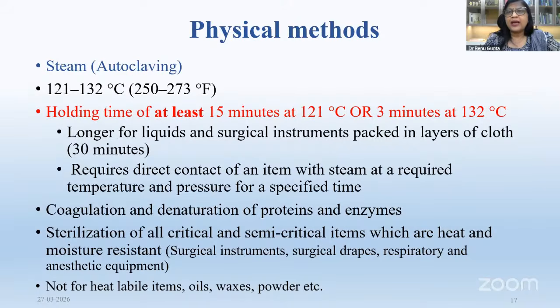This is for unpacked items like we are using in our laboratory. You are sterilizing a media. You do not put it in linen. You just put it in a flask and then put it inside the autoclave. But when you are wrapping it in layers of cloth like we do in our CSSD, we have to increase the time to 30 minutes.